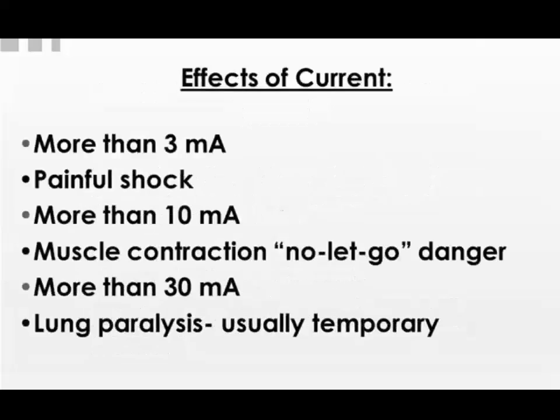Okay, effects of current, again, just training awareness. More than 3 milliamps, we get that painful shock. I think most, if not all, of us have probably experienced that at one point in time. I know I have. More than 10 milliamps, again, very, very low power, but it's that muscle contraction. You cannot let go. The muscles literally contract, and that's why, when you do your training for electrically safe work practices, if somebody's being shocked, you train them to use non-conductive material to pull them away, like a board or a fiberglass tool, something like that. By the way, a ground fault circuit interrupter, GFCI, trips at about 5 milliamps, just to put it in perspective.